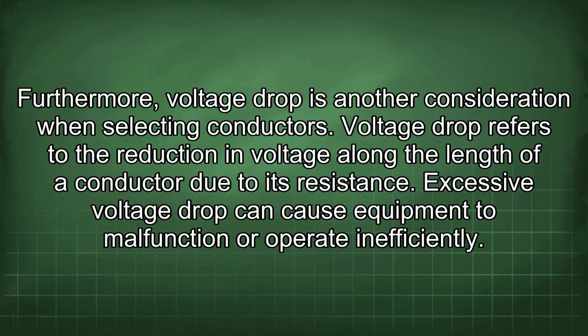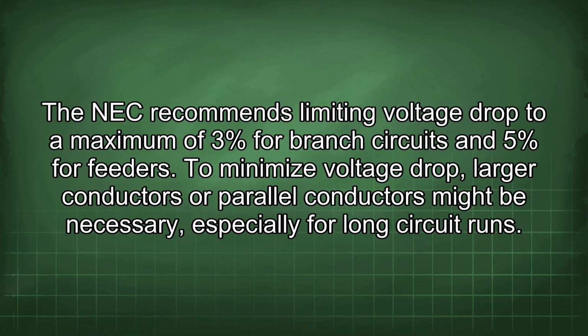Furthermore, voltage drop is another consideration when selecting conductors. Voltage drop refers to the reduction in voltage along the length of a conductor due to its resistance. Excessive voltage drop can cause equipment to malfunction or operate inefficiently. The NEC recommends limiting voltage drop to a maximum of 3% for branch circuits and 5% for feeders. To minimize voltage drop, larger conductors or parallel conductors might be necessary, especially for long circuit runs.